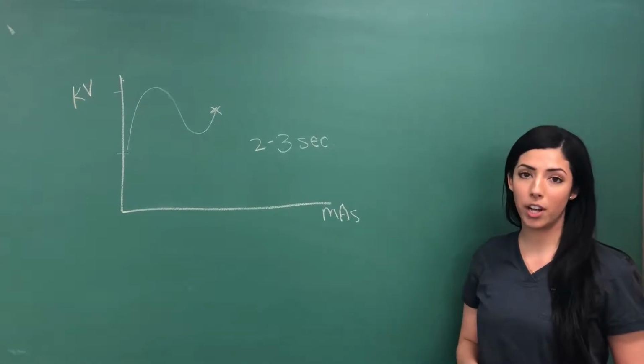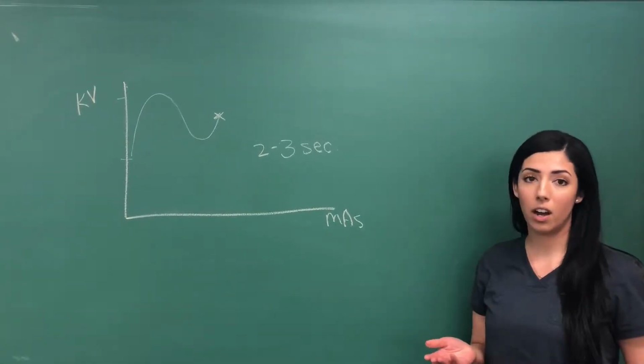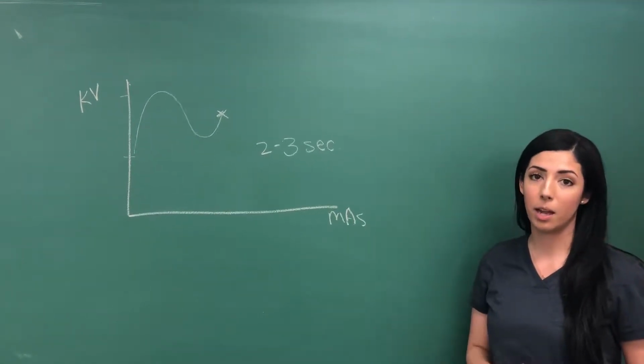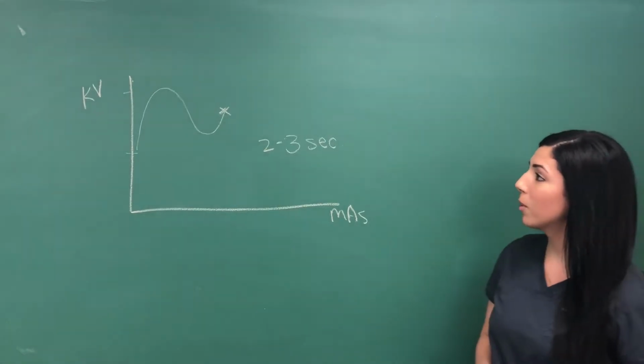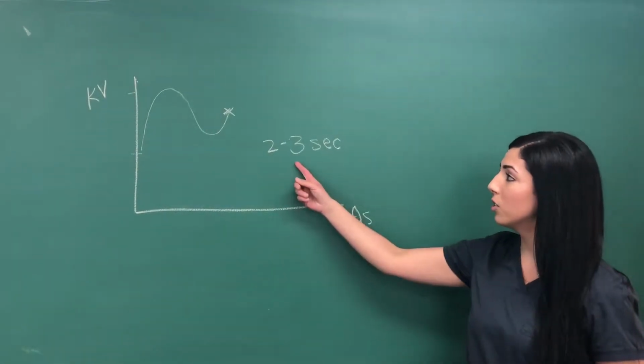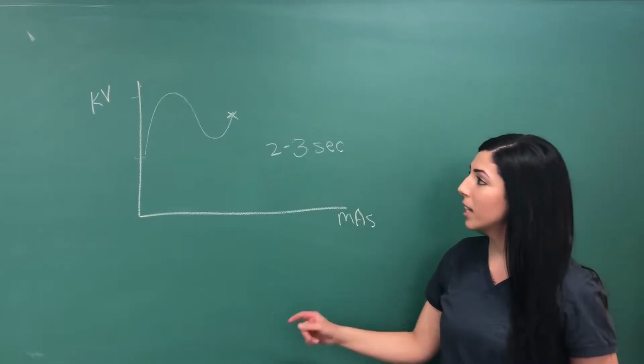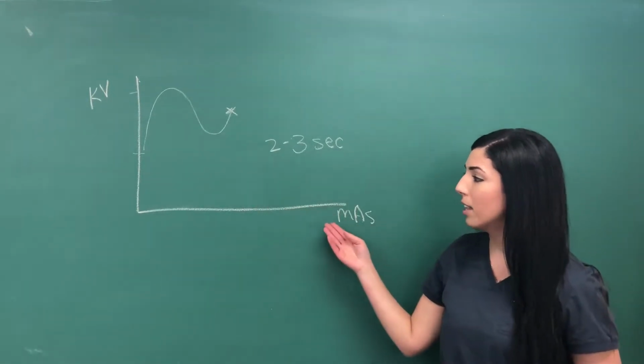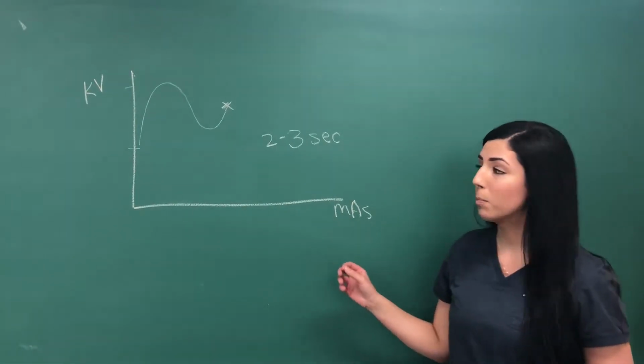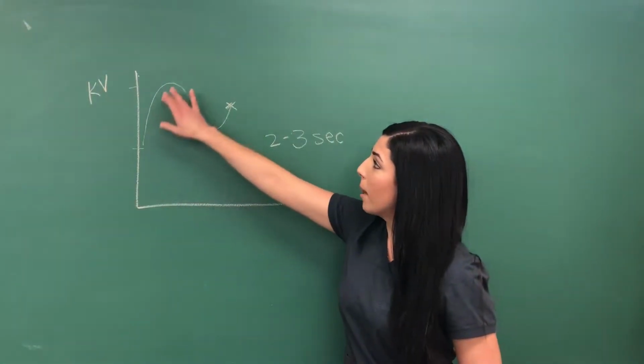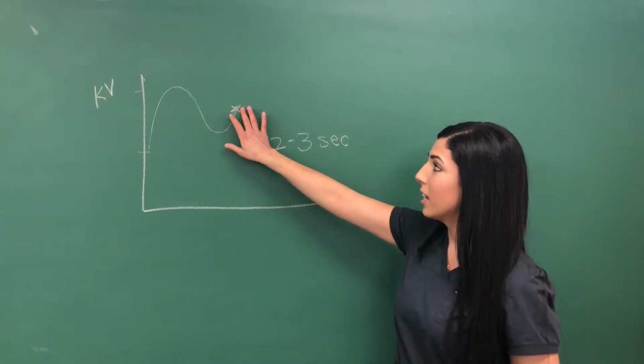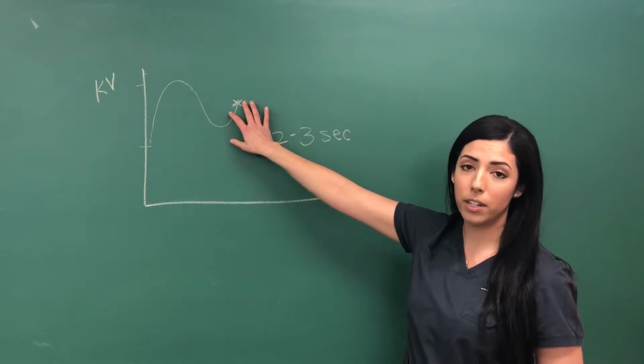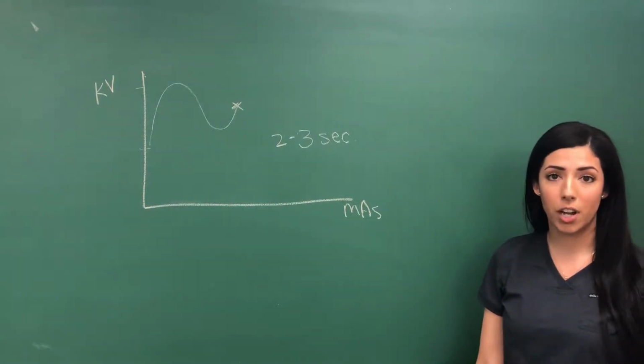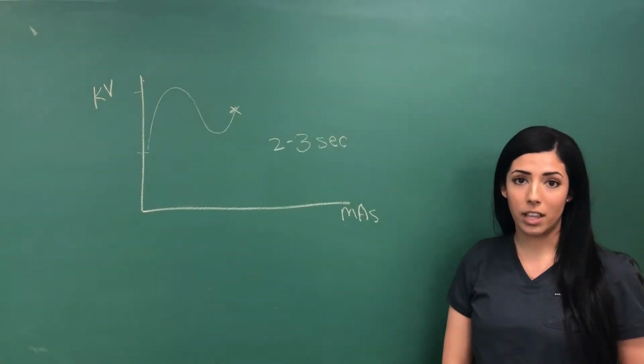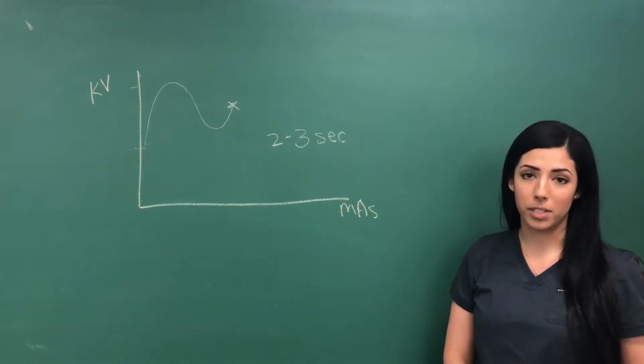So for your first shot, when you have it on auto technique, the ABC needs to come into play. So it's really important for the first exposure to do a two to three second hold. What that does is even out the kV and the mA for optimum exposure. So it'll come up and down for the technique until you get exactly what you're looking for. You only need to do that on the first shot, and that's true for the first shot of the AP or the first shot of a lateral position.